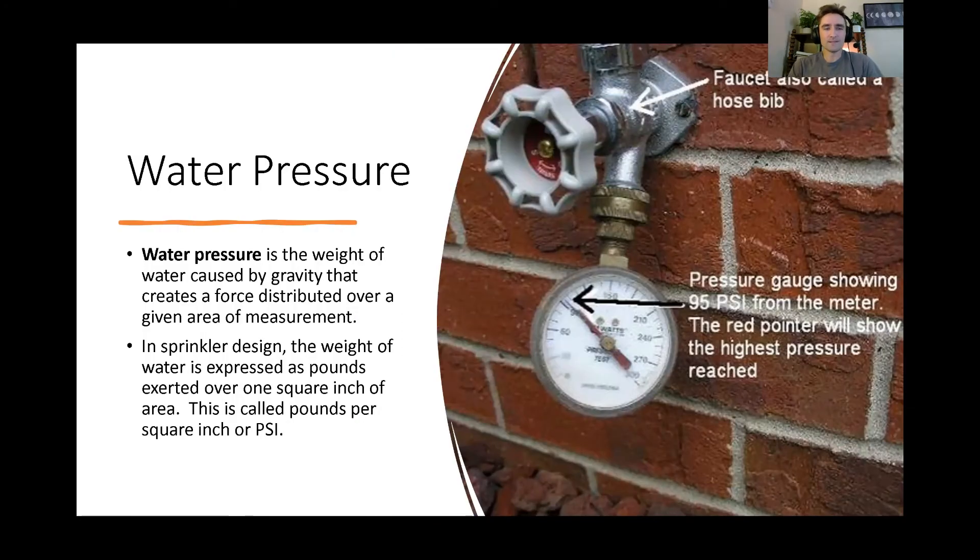Water pressure is the weight of water caused by gravity that creates a force over a specific area. That's the technical definition. And that's hard to understand what it's even talking about. But in sprinkler design, we express this weight of water as pounds per square inch, psi. So for every square inch of area, how many pounds of water is on top of it, pushing it down. And here you can see a hose bib with a pressure gauge. So you put that right up and you get a pressure reading of 95 psi. That is static, does not change. And so every house will have a different water pressure coming into the house.